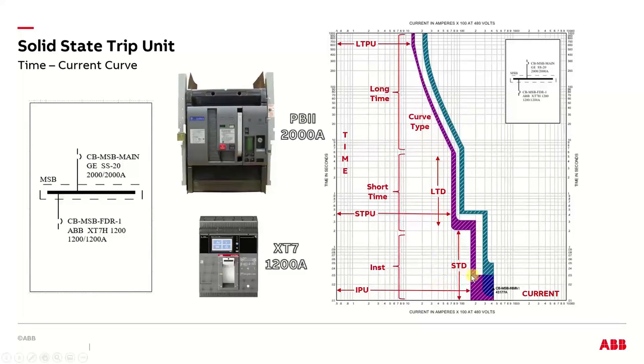instantaneous pickup. And so you can set your instantaneous really high to get over usually a magnetic inrush on a motor or a transformer. Typically, you can get a 10X. There are breakers with larger, you can get a 13 and a 15X breaker. But typically, it's a 10 to 1 ratio. So with your long time pickup of 100 amps, your instantaneous maximum would be 1,000 amps. That's a typical range. But all these are adjustable.